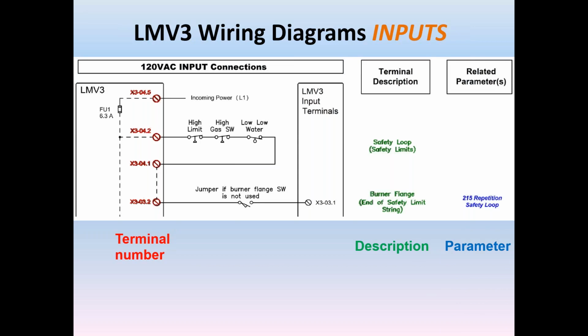This particular one has a parameter associated with it, number 215, and that's a repetition counter on the safety loop. So you can configure this input with the parameters, and that will be done. We will explain how the parameters affect the terminals when we do the parameter section next week. But this tells you when you're wiring it in, what parameters are needed to be configured so that the input acts the way you want for your particular application.